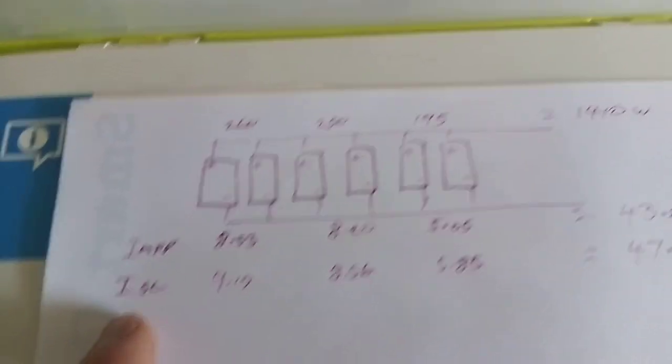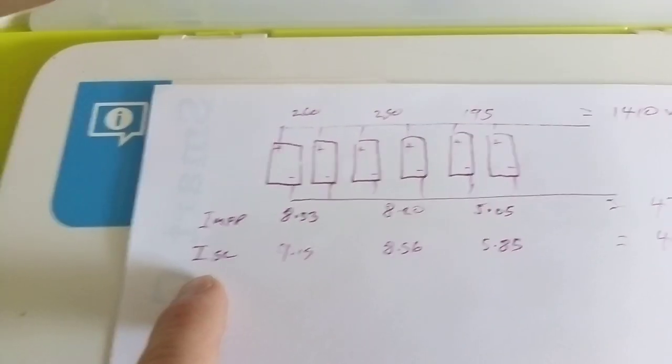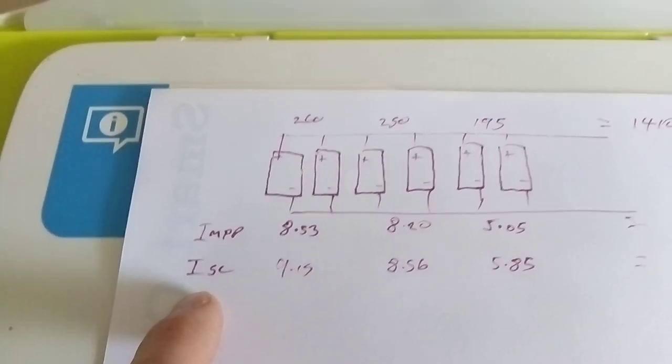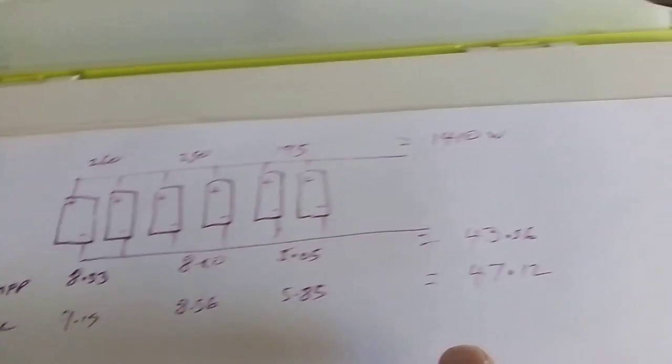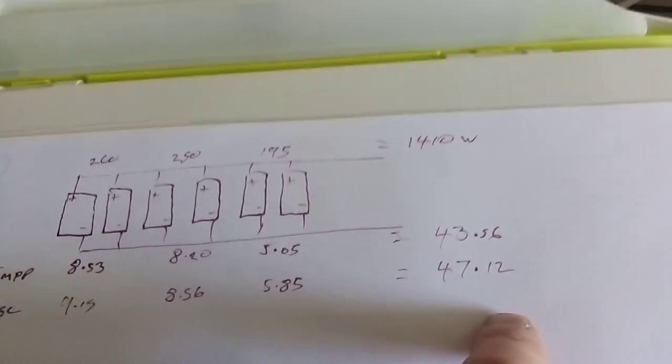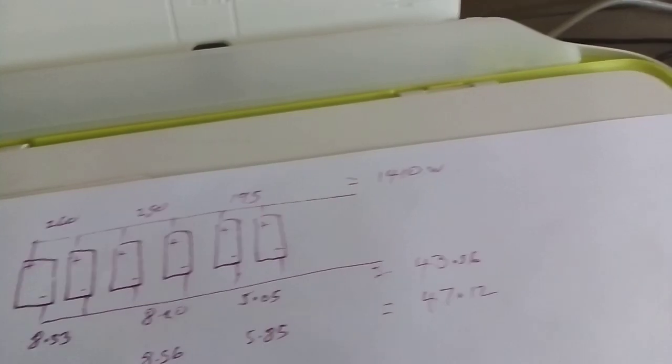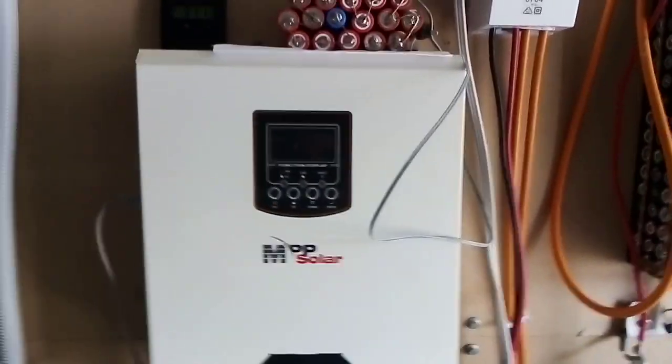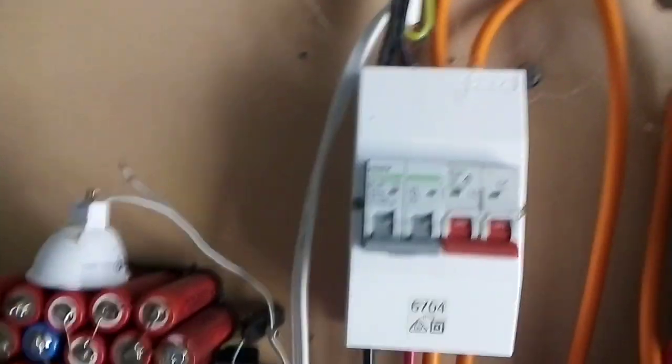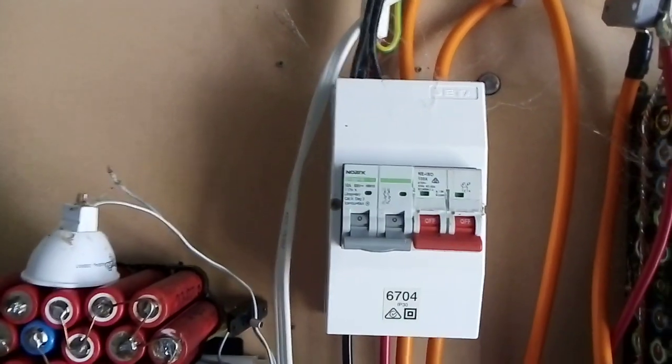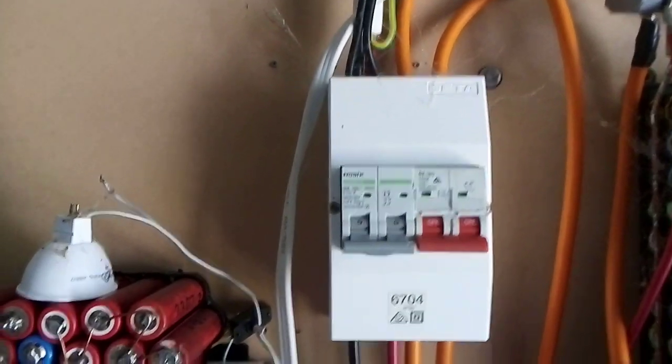I've calculated it using the max short circuit current, which is a lot higher, because I wanted to be well within the inverter parameters. I didn't want to blow up a $500 unit. As long as you've got that in place and you've got a circuit breaker in line with the instructions for the inverter - a 50 amp breaker.